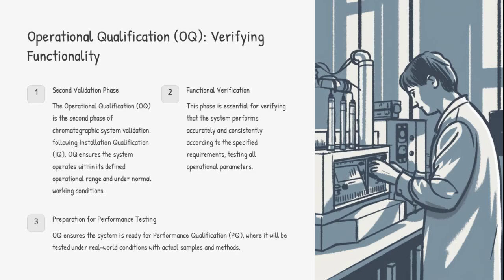Operational qualification, OQ, is a critical phase for verifying that the system performs accurately and consistently according to specified operational parameters. It includes second validation phase, functional verification, and preparation for performance testing, ensuring the system is ready for real-world conditions.